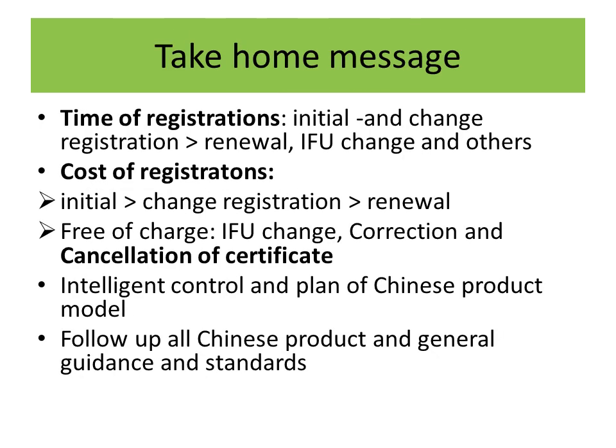As expected, the renewal process is quite short, 1 to 2 months. However, manufacturers are suggested to submit the dossier 6 months before the expiration date. The time for initial and change registration is the same at the authority side. Only the classification of the product makes a difference, Class 3 longer than Class 2. The cost of initial registration is a bit more expensive than change registration and renewal. The other applications are even free of charge.